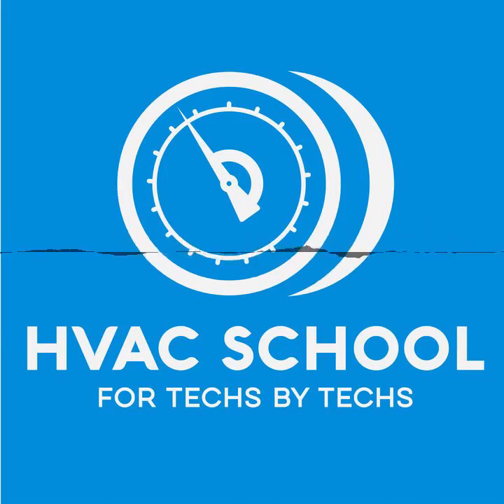Should you change it regularly? Yeah, I would say if you're not billing the customer for the vacuum pump oil and changing it each time, then what are you doing? It's something you can do anyway. If I have somebody paying for the oil, I'm going to keep my pump oil as clean as possible and change it after every use. Maybe at most I might go three times for typical system evacuations, but I've got oil in the vacuum pumps at the office, because I'm always evacuating clean tanks and things like that, that I'd let go for a year before I change it.